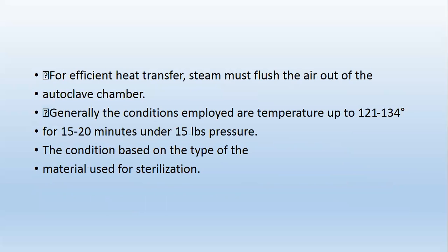For efficient heat transfer, steam must flush the air out of the autoclave chamber. Generally, the conditions employed are temperature of 121 to 134 degrees for 15 to 20 minutes under 15 lbs pressure. The condition is based on the type of the material used for the sterilization.